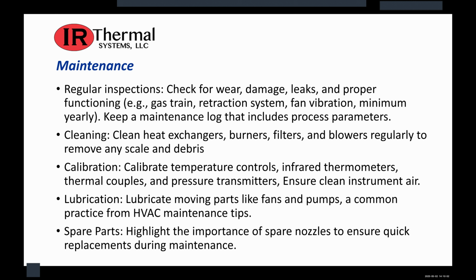Also, from a calibration standpoint, you want to make sure your temperature controls are calibrated, your infrared thermometers are calibrated, thermocouples, pressure transmitters, and you want to ensure that you have clean instrument air. This is always critical. And make sure you have the right FRLs, or filter regulators, in place.